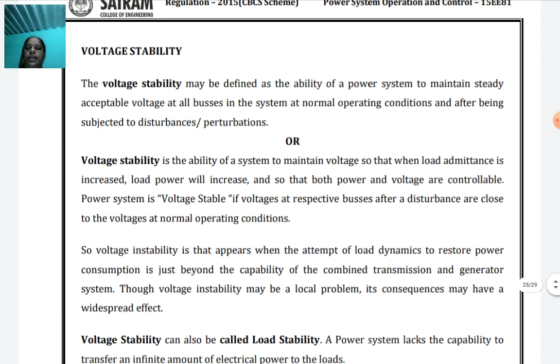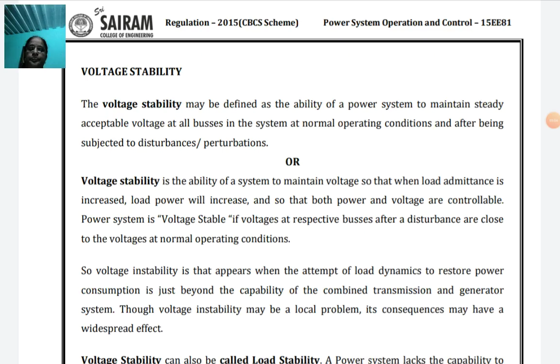Then voltage stability. Voltage stability may be defined as the ability of a power system to maintain steady acceptable voltage at all buses in the system at normal operating conditions and after being subjected to disturbances. Voltage stability is the ability of the power system to maintain the voltage when load admittance is increased or the load power increases, so that both power and voltage are controllable. A power system is voltage stable if the voltages at respective buses after a disturbance are close to the voltages at normal operating conditions. Voltage instability appears when the attempt of load dynamics to restore power consumption is just beyond the capability of the combined transmission and generation system.